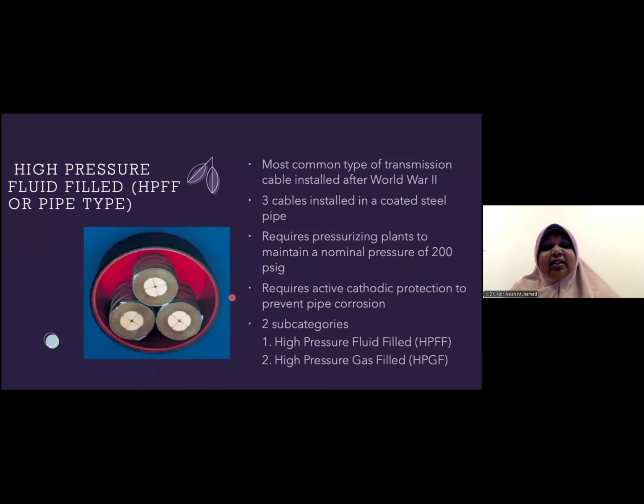Then the last type of cable is the high pressure fluid filled cable, which is the pipe type. Inside the pipe, we have three-phase cable. It was the most common type of transmission cable after World War II. There are three cables installed and coated in the steel pipe. It is a pressurized line. At the incoming end, there are plants to maintain the pressure inside the pipe.